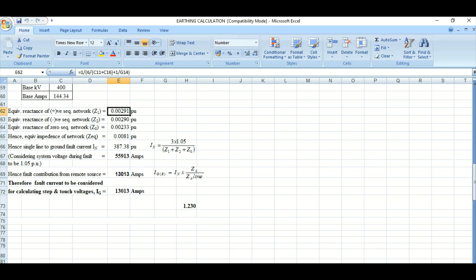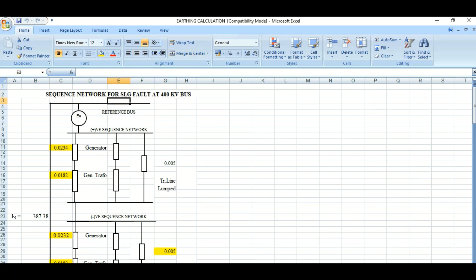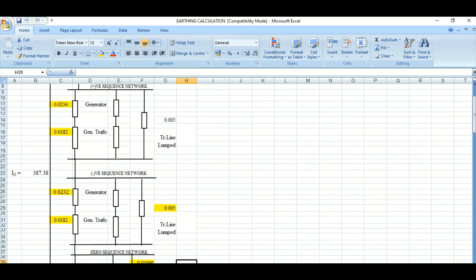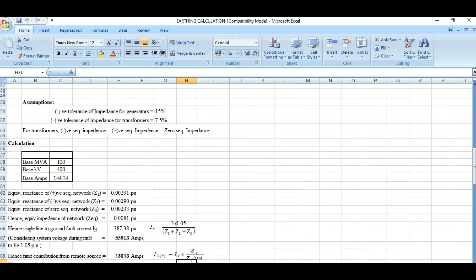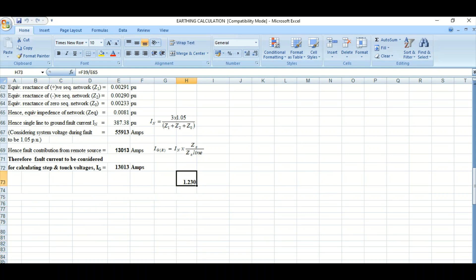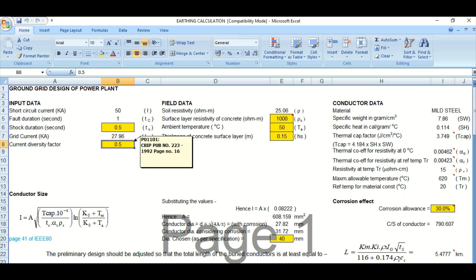Next is grid current IG. You need to calculate the grid current. I will cover how to calculate the grid current in a separate video — drop a comment if you want. This is a practical example from an existing project. Using the positive and negative sequence network, we calculate the grid current. The current diversity factor is 0.5, and shock duration and diversity factor values are taken from CBIP.